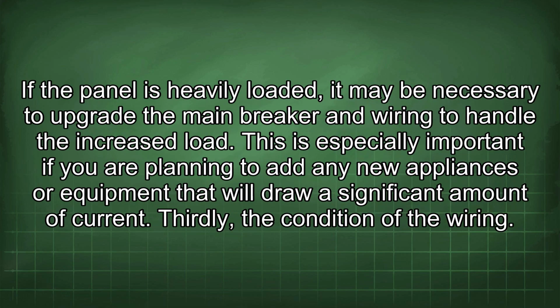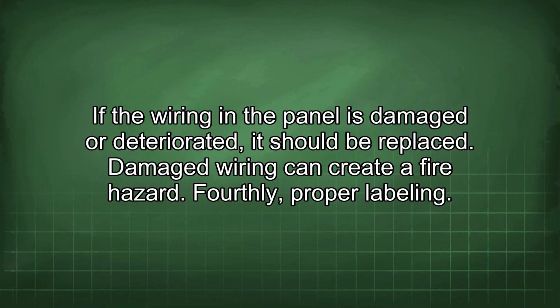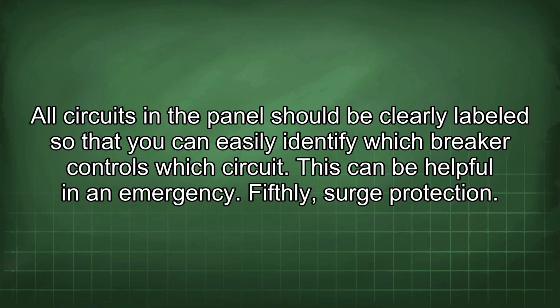If the panel is heavily loaded, it may be necessary to upgrade the main breaker and wiring to handle the increased load. This is especially important if you are planning to add any new appliances or equipment that will draw a significant amount of current. Thirdly, the condition of the wiring. If the wiring in the panel is damaged or deteriorated, it should be replaced. Damaged wiring can create a fire hazard. Fourthly, proper labeling. All circuits in the panel should be clearly labeled so that you can easily identify which breaker controls which circuit. This can be helpful in an emergency.